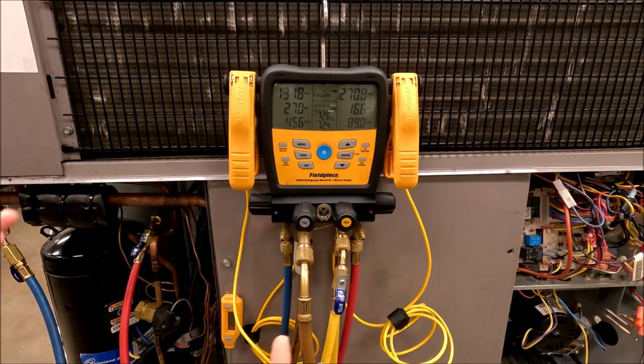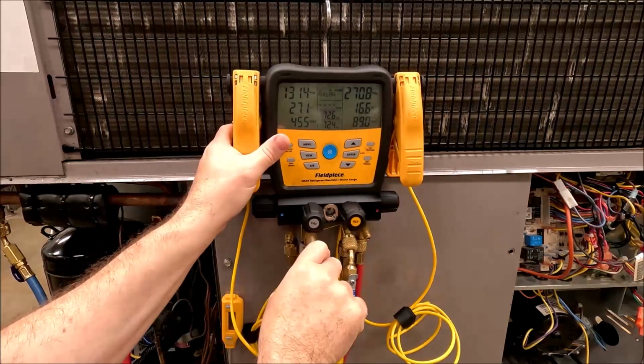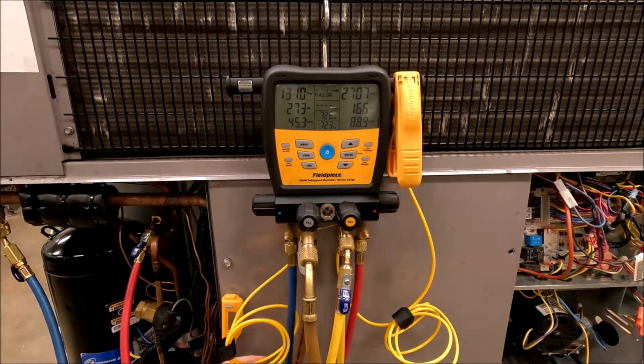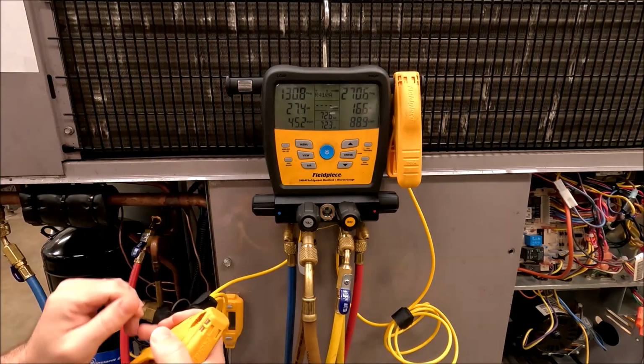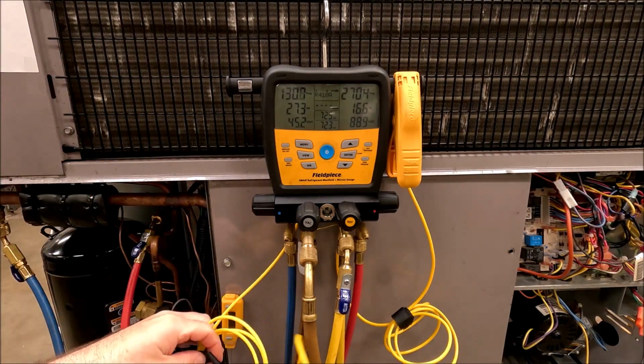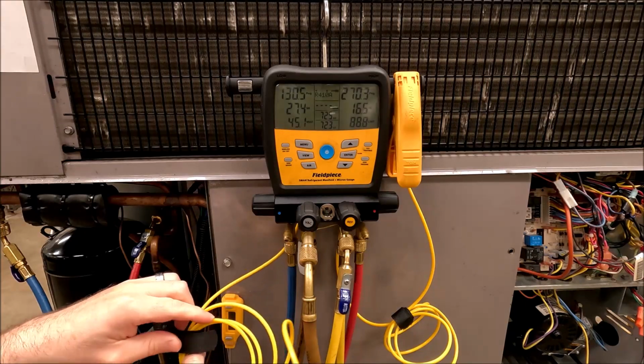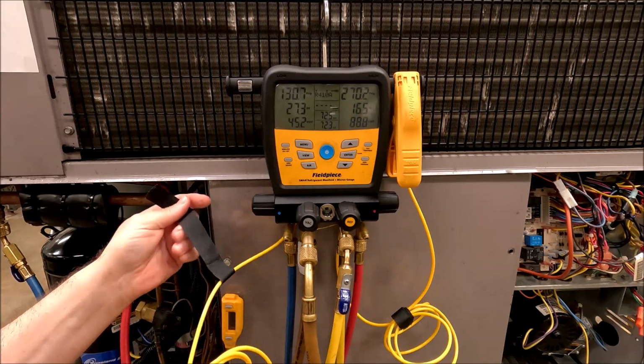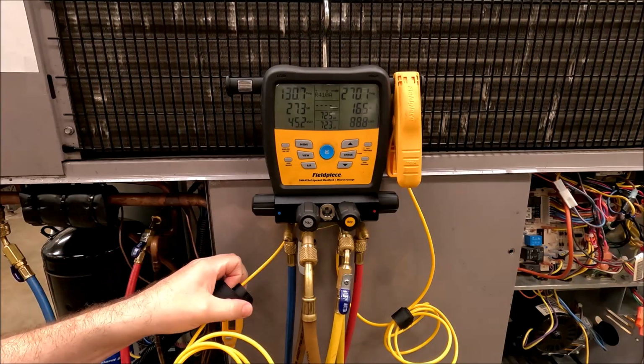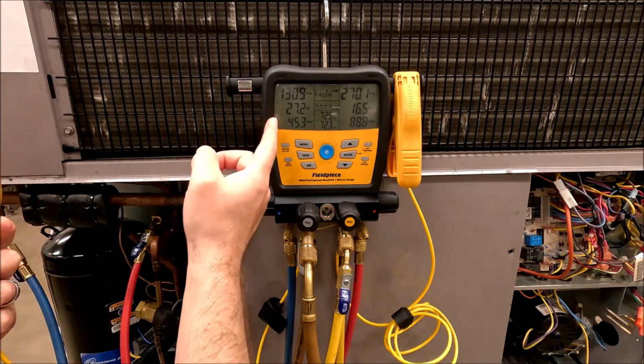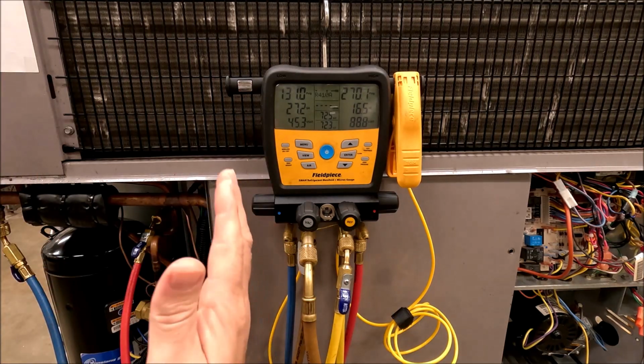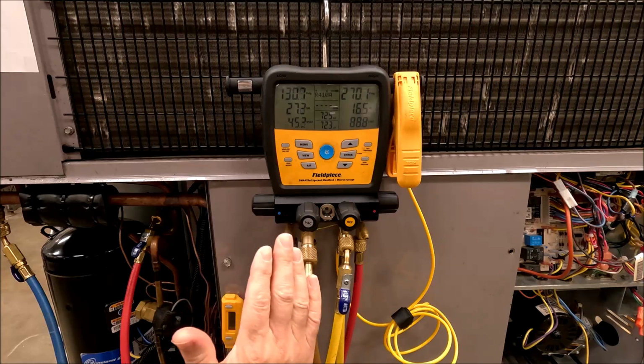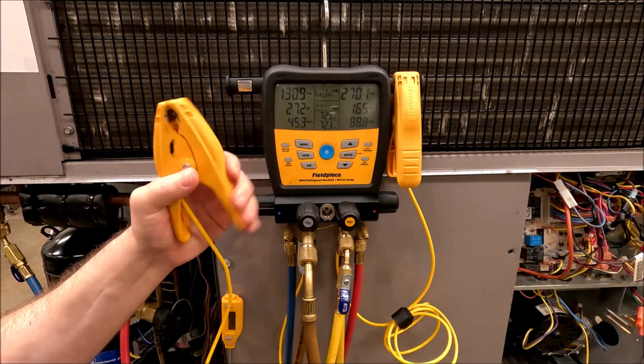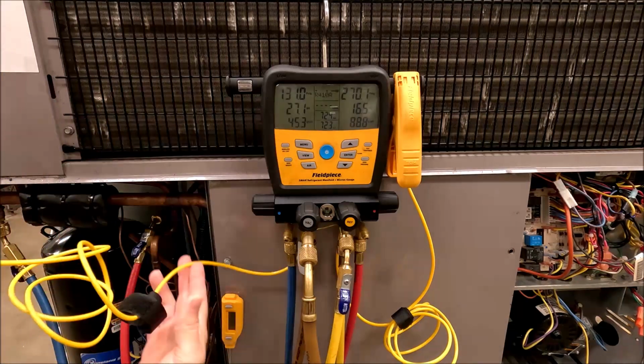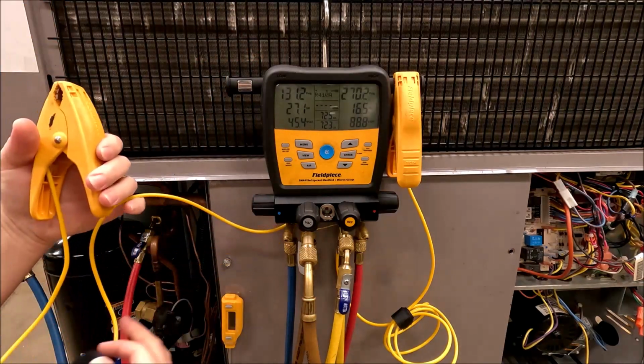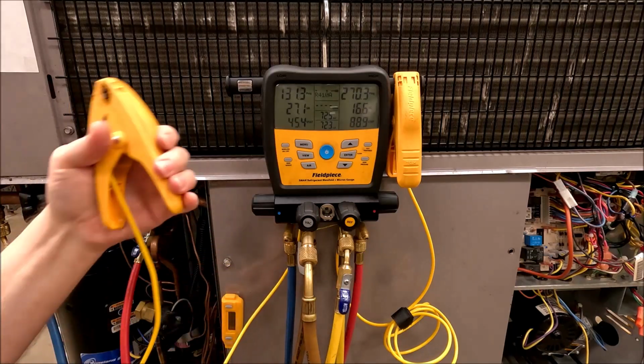Now, if you've never seen these gauges, which I don't know who hasn't already, but just in case you're new and don't have digital gauges, this one actually comes with built-in pipe clamps, whereas the last unit I had a pipe clamp with an adapter that would plug into my meter, since I had a temperature function on my meter. All right, so whichever, doesn't matter. The good thing is this guy will do the math for you if you tell it the right numbers. So wherever you put these clamps is where you're telling it. This is on the low side of my system where the pipe clamp plugs in. So this is going to be for my superheat.